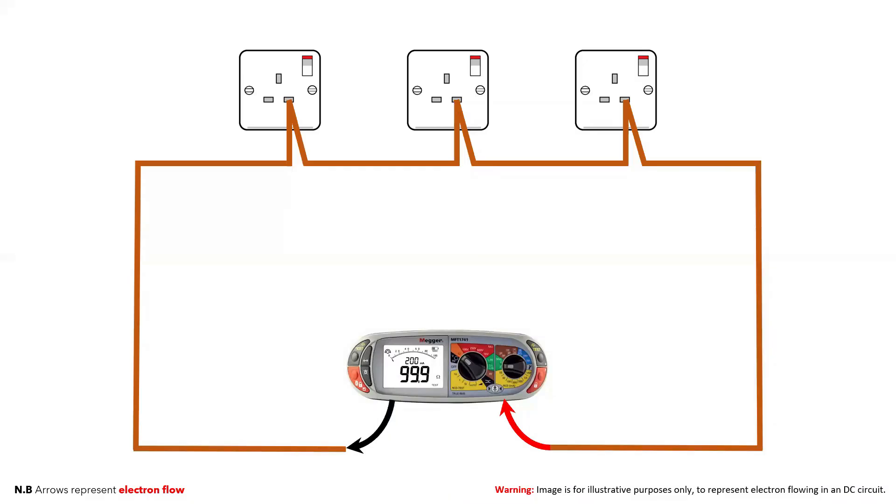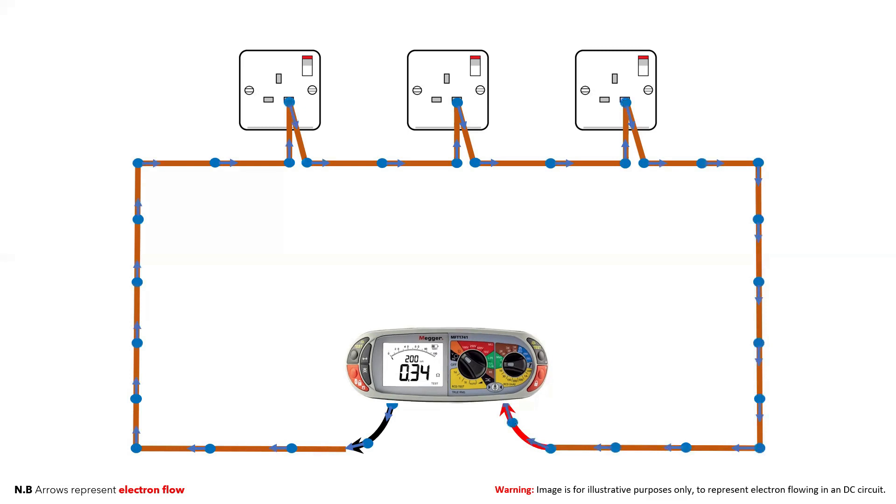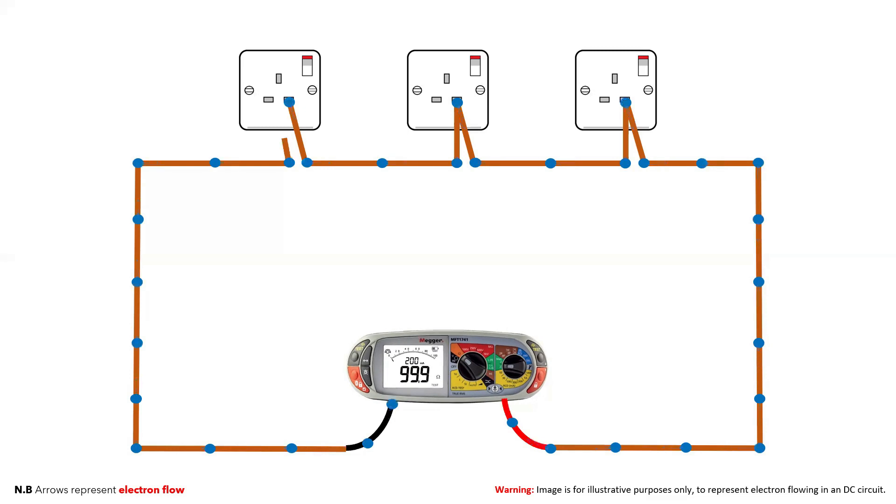When we connect the MFT into the little R1 circuit, if the circuit is complete, the electrons with their negative charge flow from the negative terminal around the circuit and are attracted back to the positive terminal. The MFT can measure that flow and give us a reading, which in this example is 0.34 ohms. If there was a break in the circuit, the electrons would not flow and the MFT would show an out of range reading of greater than 99.9 ohms.